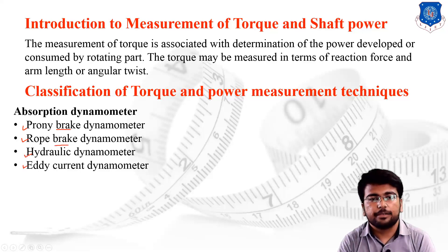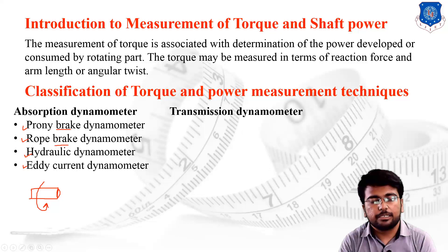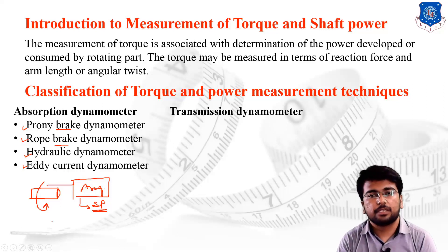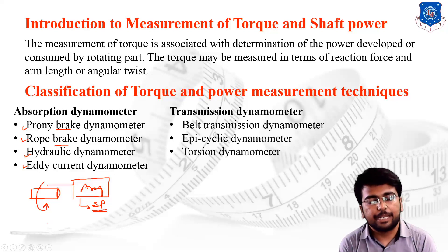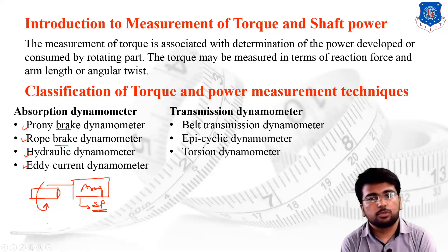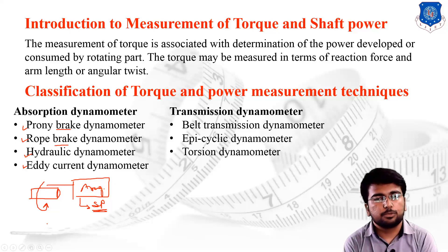The second category is the transmission type dynamometer, in which power generated by the shaft is simply transmitted to another arrangement that measures the shaft power. The dynamometer itself does not absorb the power but transfers it to another mechanical setup. Examples include the belt transmission dynamometer, which uses a belt-pulley arrangement to transfer shaft power from one position to another, and the epicyclic dynamometer, which uses an epicyclic gear train to transmit shaft power.